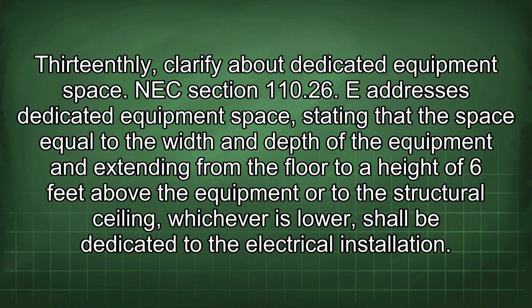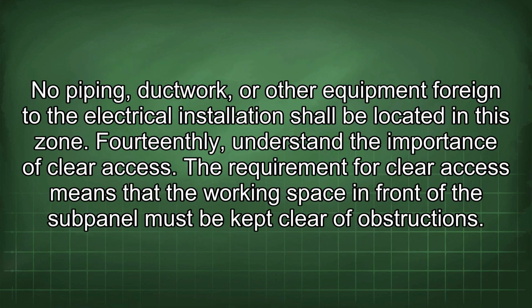NEC Section 110.26(E) addresses dedicated equipment space, stating that the space equal to the width and depth of the equipment and extending from the floor to a height of 6 feet above the equipment or to the structural ceiling, whichever is lower, shall be dedicated to the electrical installation. No piping, ductwork, or other equipment foreign to the electrical installation shall be located in this zone. 14thly, understand the importance of clear access.